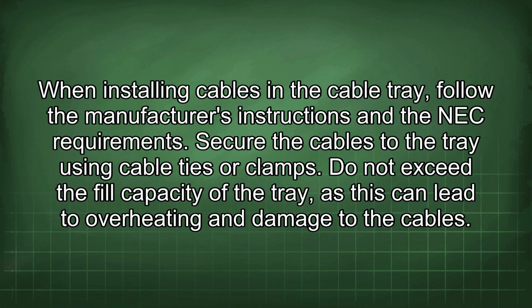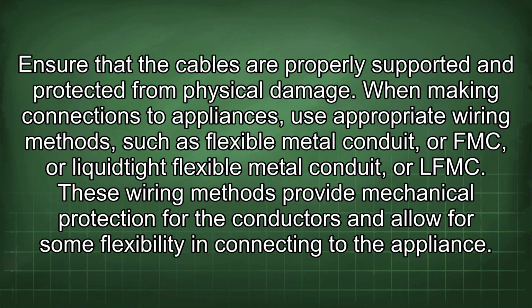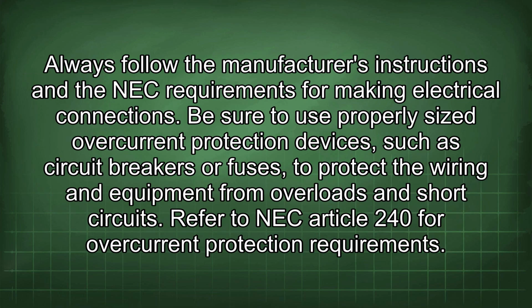When installing cables in the cable tray, follow the manufacturer's instructions and the NEC requirements. Secure the cables to the tray using cable ties or clamps. Do not exceed the fill capacity of the tray, as this can lead to overheating and damage to the cables. Ensure that the cables are properly supported and protected from physical damage. When making connections to appliances, use appropriate wiring methods such as flexible metal conduit, or FMC, or liquid-tight flexible metal conduit, or LFMC. These wiring methods provide mechanical protection for the conductors and allow for some flexibility in connecting to the appliance. Always follow the manufacturer's instructions and the NEC requirements for making electrical connections.